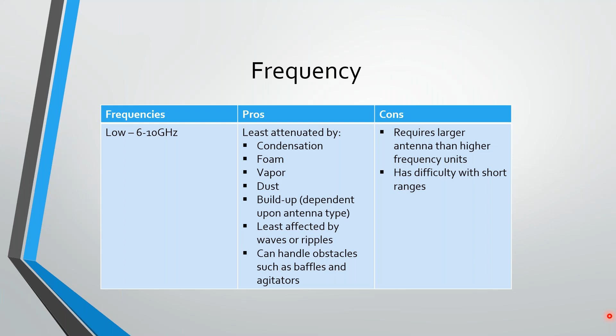In the mid frequency, we still have pretty good reliability when it comes to condensation, foam, vapor, dust. We're still pretty good with buildup. Of course, here in the mid frequencies, we can use something like the teardrop antenna. Teardrop antennas are pretty much immune to buildup, whether that be used on a powder or solid, or on a liquid application, which has a lot of condensation. We still get pretty good reliability when it comes to tuning out waves and ripples. We can still tune out obstacles such as baffles. But one big advantage is we're able to use smaller antennas than the lower frequency at this point.